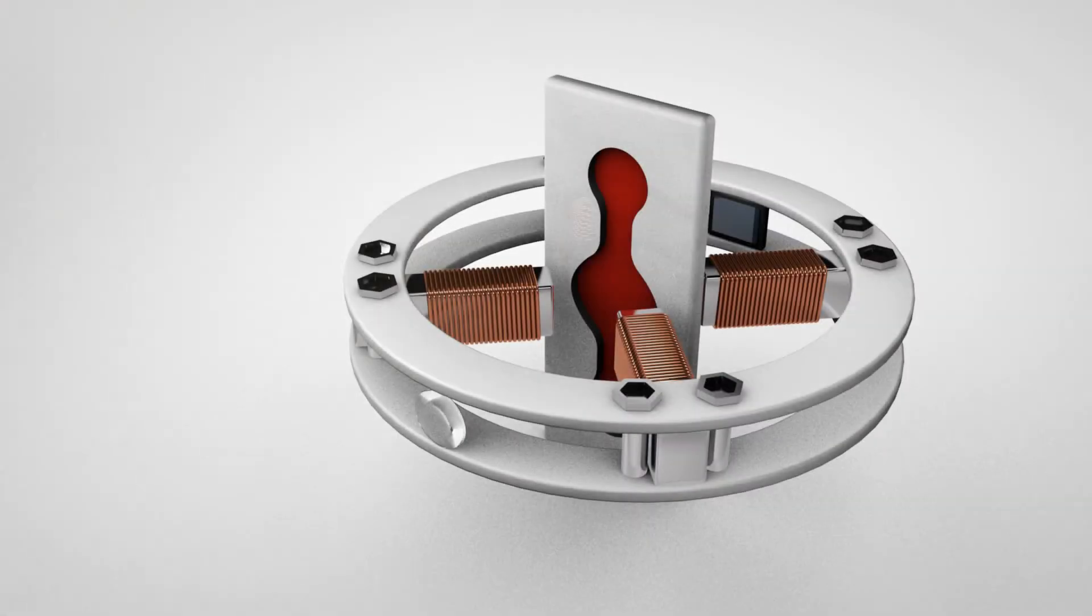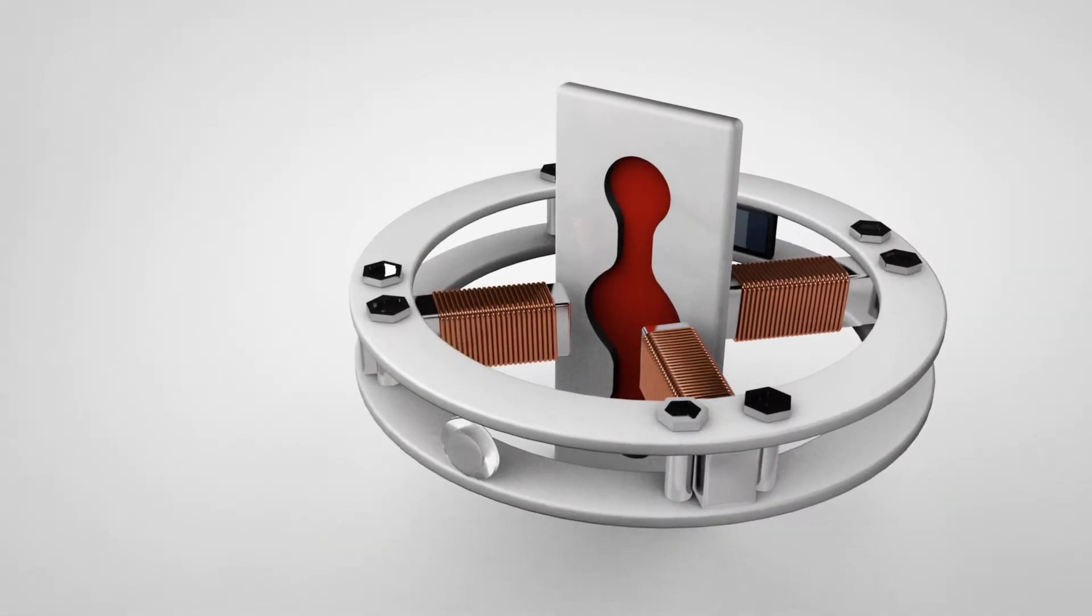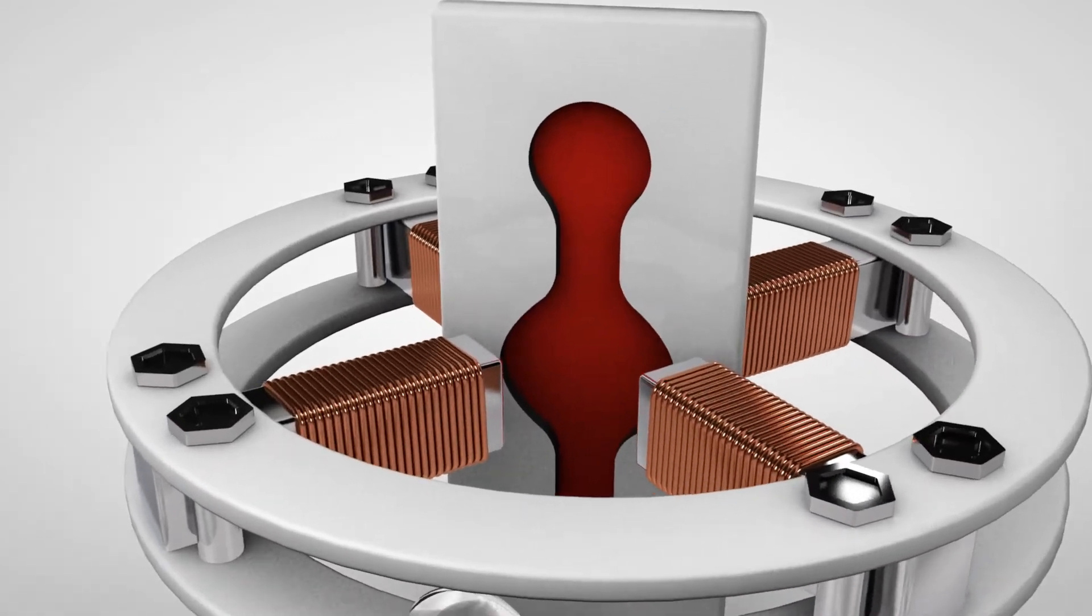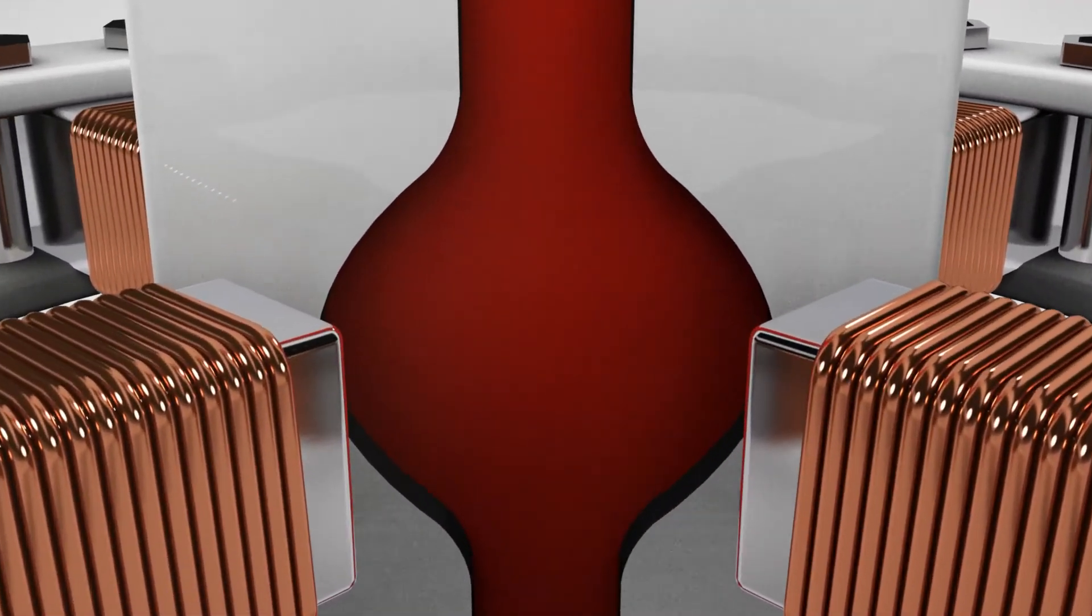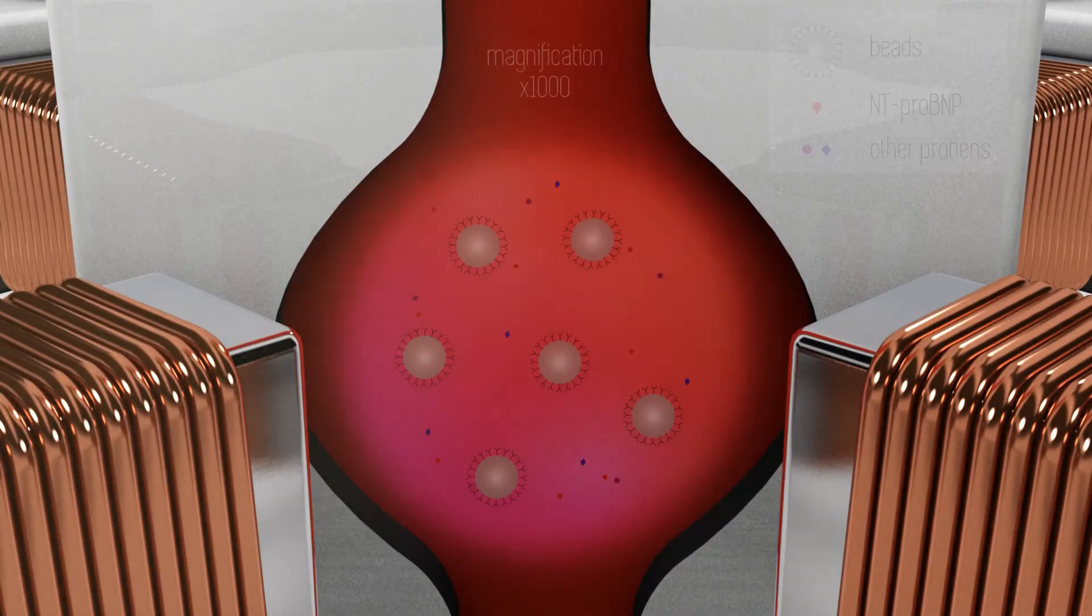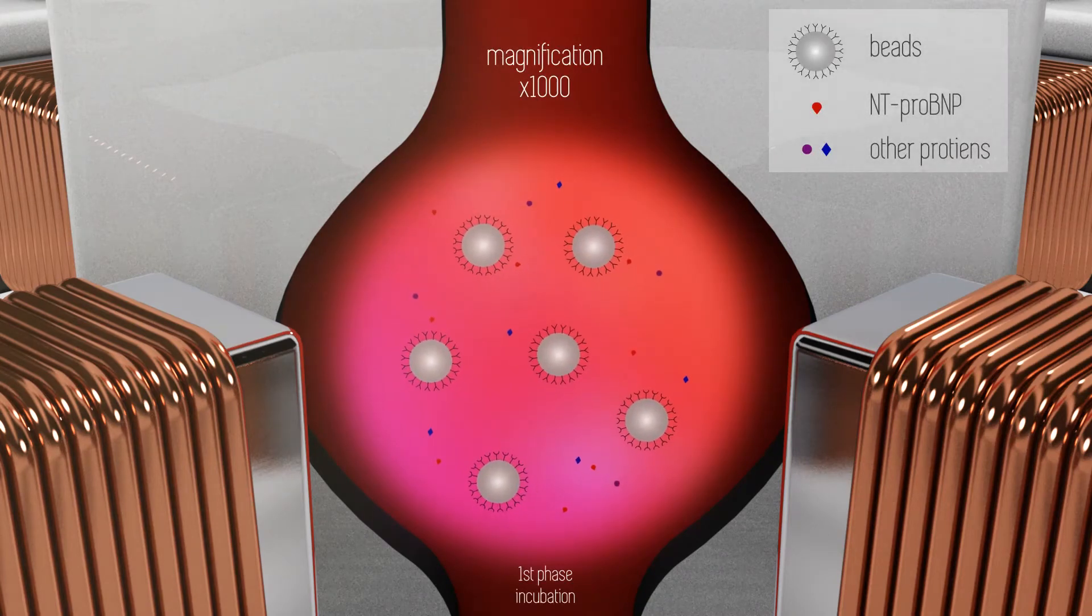Once the plasma reaches the reaction chamber, the dried magnetic particles in this chamber will dissolve. The magnetic particles are coated with antibodies, to which the biomarker binds during the first phase, the incubation phase.